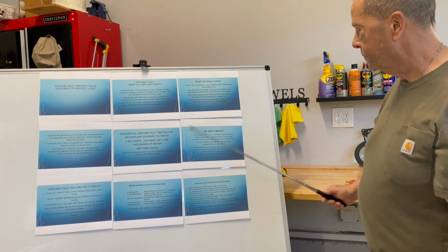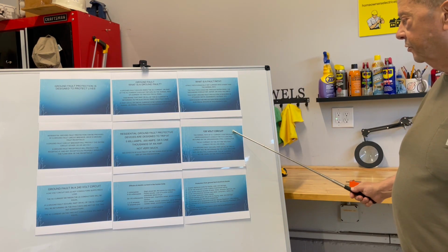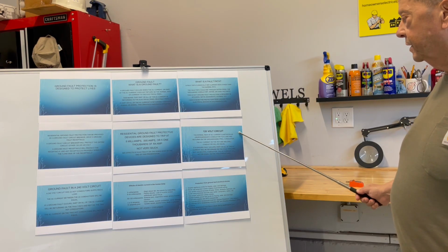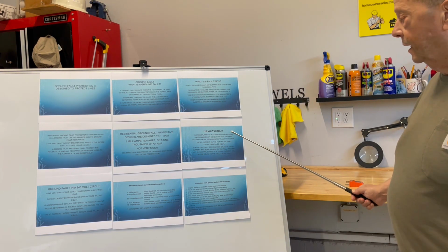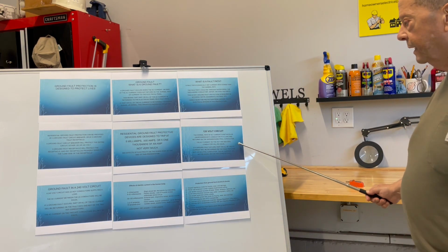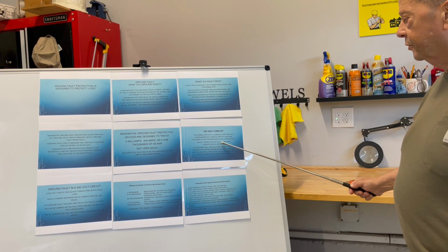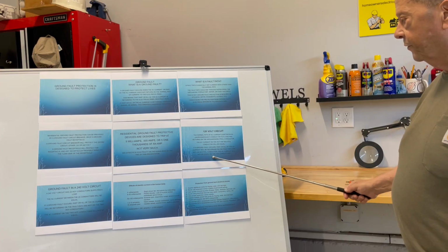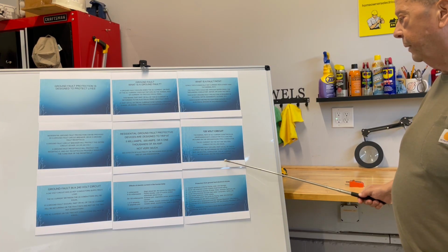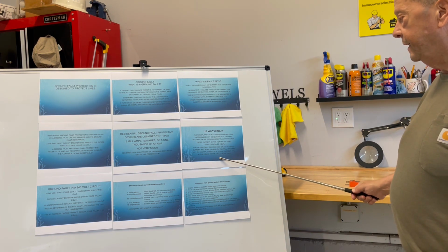In a 120 volt circuit, the normal path of AC current is between an ungrounded hot conductor to a load and returns on the grounded neutral conductor. Remember I told you back when you were looking at me like everything was boring? Now it's starting to make a little bit of sense to you, maybe. The AC current on the hot and neutral conductor will be equal. If a ground fault occurs, part or all of the AC current will be returning on the fault path and not on the neutral. The AC current will not be equal on the two conductors.